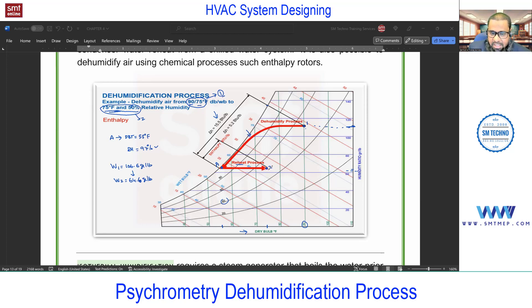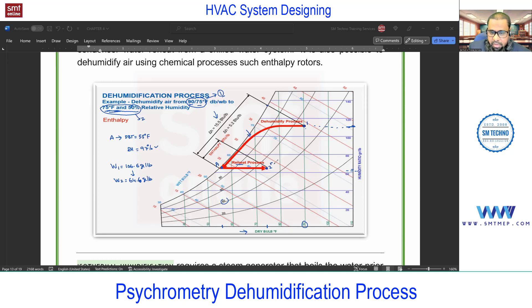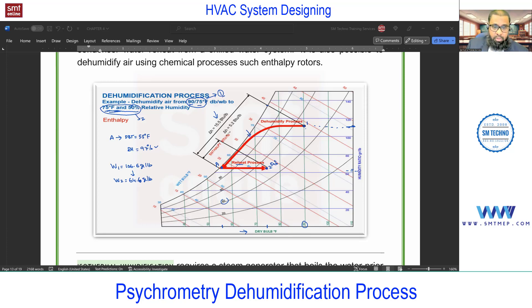At point 2 you will get the desirable conditions: 75°F dry bulb. We increase the temperature for two reasons: first, to maintain the required temperature; second, to maintain the RH, because as temperature increases the holding capacity of moisture increases and RH decreases. At point 2 the RH is 50%. This process is called dehumidification with reheat.